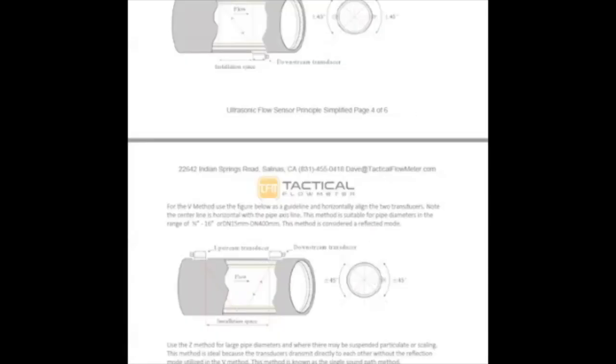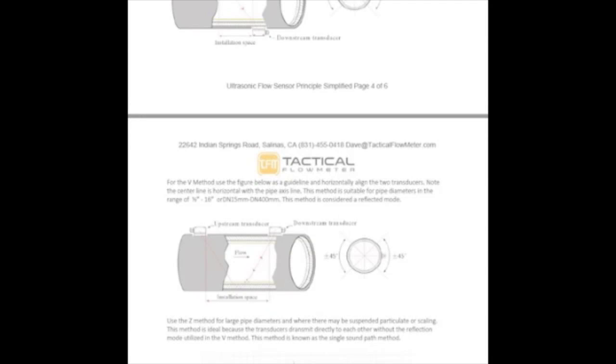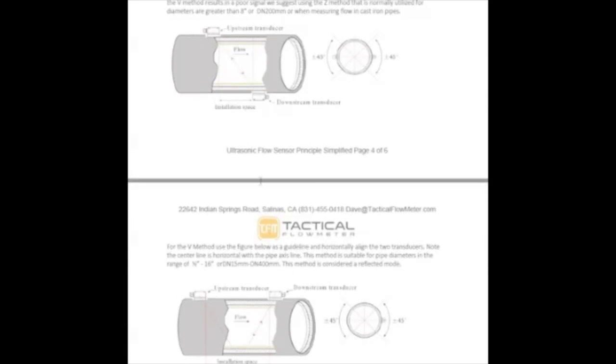So we want to show the two different methods. This is the most common method we will suggest that folks use, from half-inch to 16-inch pipes, most commonly used. And then this explains why you would use this kind of system. If the signal's poor or you're measuring the flow in greater than eight-inch or measuring the flow in cast-iron pipes, you would be using this kind of direct shot. Not a ricochet like this, but the direct shot.